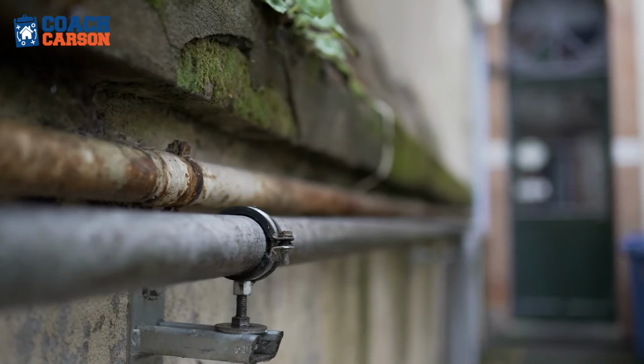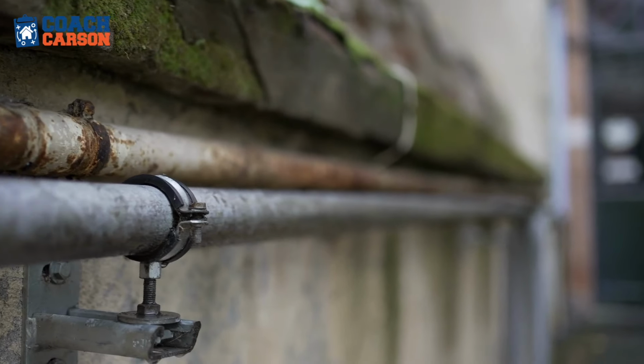So then the water comes in, and what is it, right? If it's old, it might be old steel pipes, and those are not great. We have some of those in my area. Those do corrode on the inside, and then that corrosion balls up and plugs all sorts of different valves up, and eventually that just has to be completely removed. So be careful. If you have old pipes that look like they're painted or chipped, you're probably not going to see the corrosion on the outside, but you will on the inside.